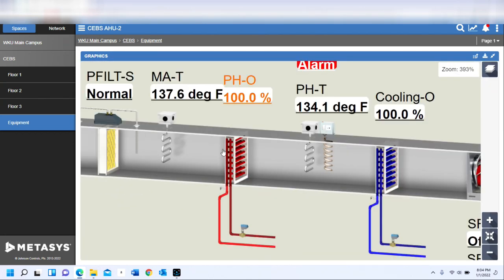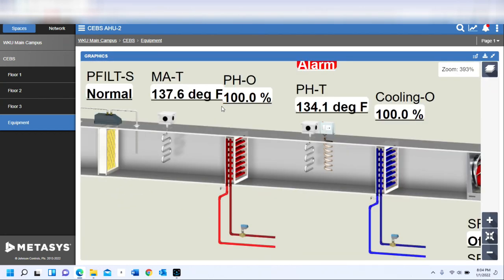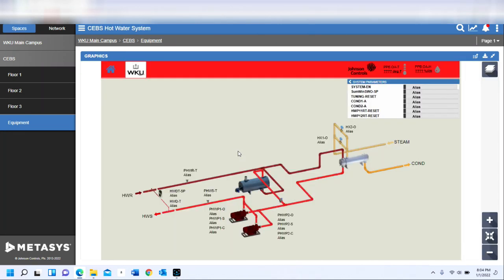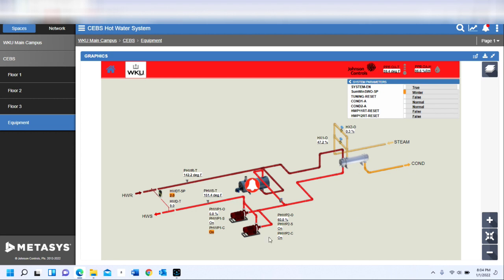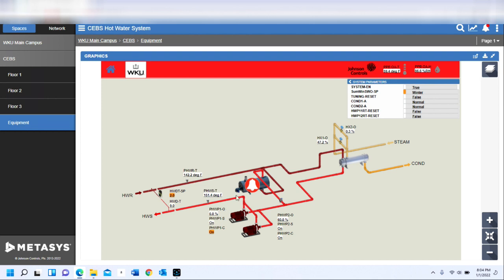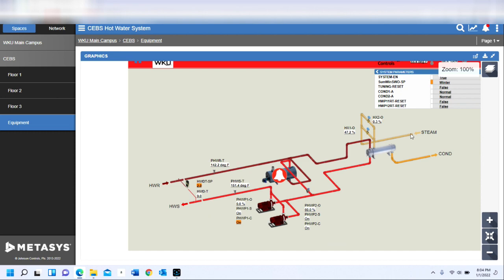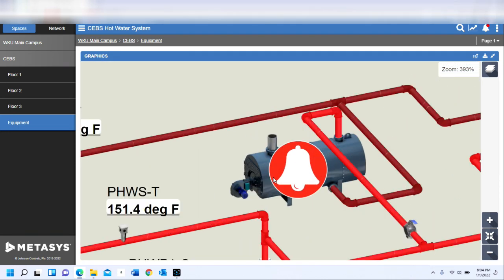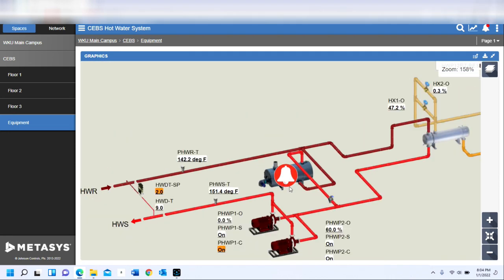The same can be done—I'm just going to go back to my previous screen and zoom back in—and the same can be said about the preheat system as well. I'm going to pull up the hot water system because I have it linked to that particular graphic within the air handler. You can see here we do have an alarm flag on this boiler, but of course we're currently running the steam system. This boiler is disabled.